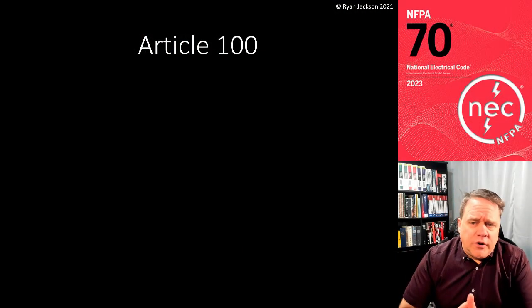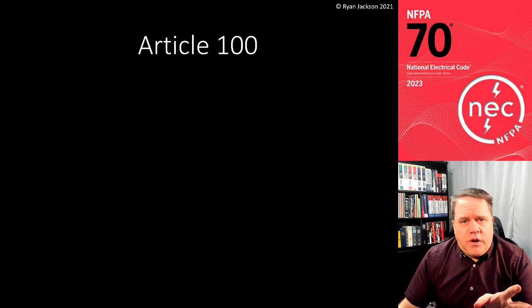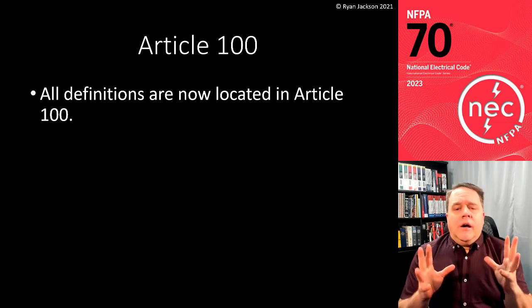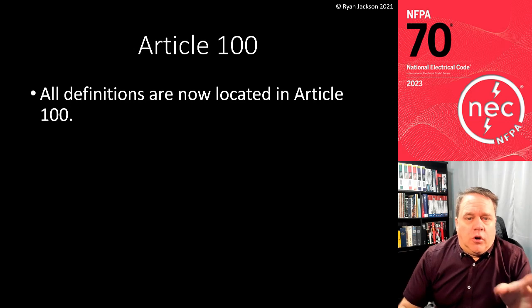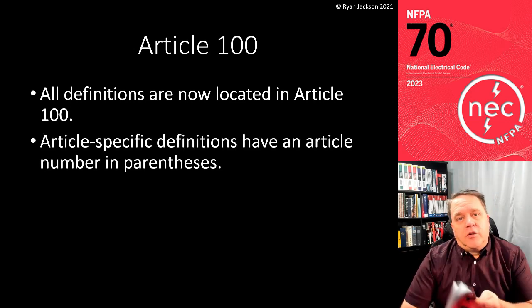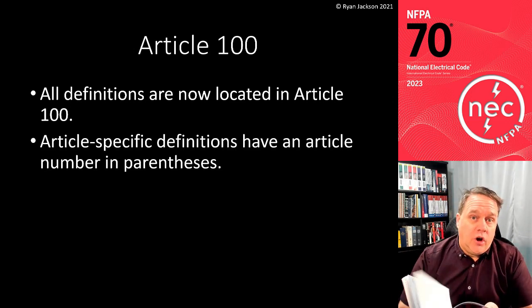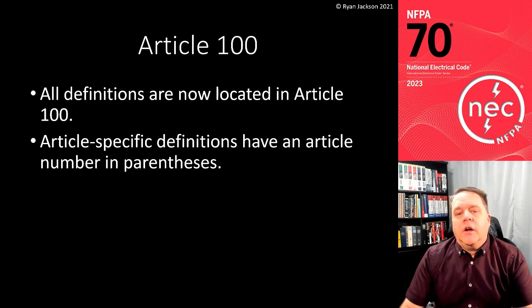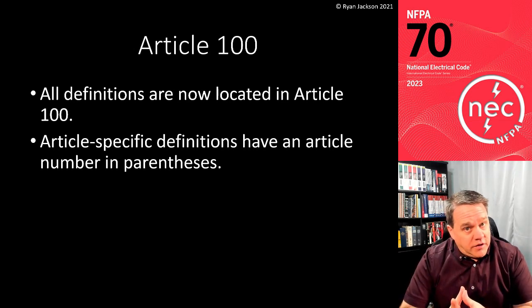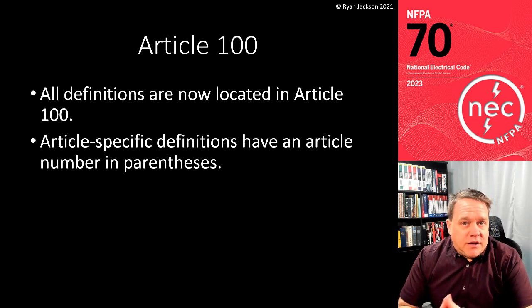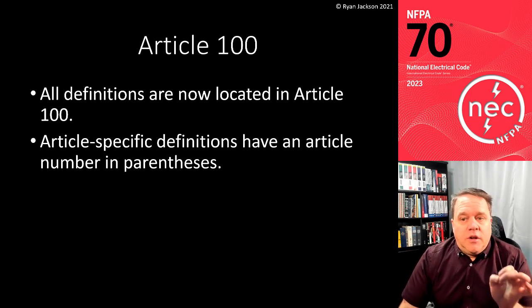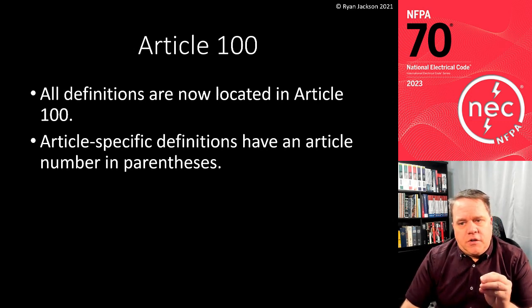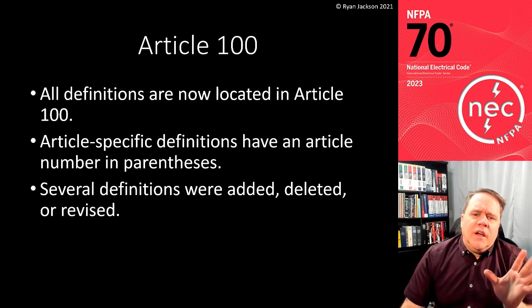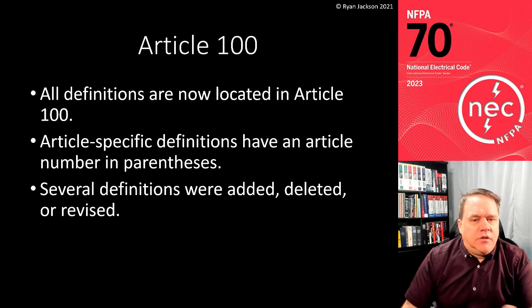Another thing that we had, and I'll go ahead and move over to the presentation here, Article 100. Just like we had in the 2023 version of the National Electrical Code, all definitions are now located in Article 100. For a small standard like this, probably a good thing. They should all be in the front of the standard, in my opinion. Again, just like the 2023 NEC, article-specific definitions now have an article number in parentheses, and I'll show you an example here in just a minute. And of course, several definitions were added, deleted, or revised.